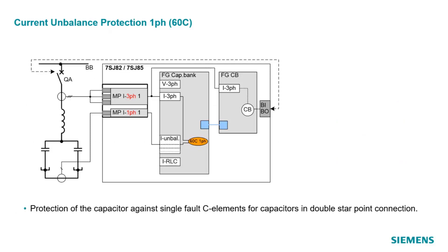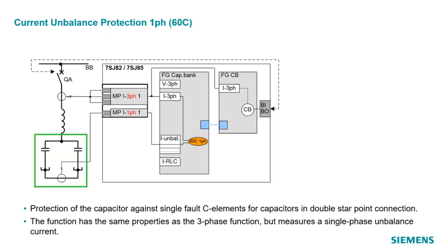The single-phase unbalanced protection protects the capacitor against single faulty capacitor elements for capacitors in double star point connection. The function has the same properties as the three-phase function we saw before, but measures a single-phase unbalanced current.